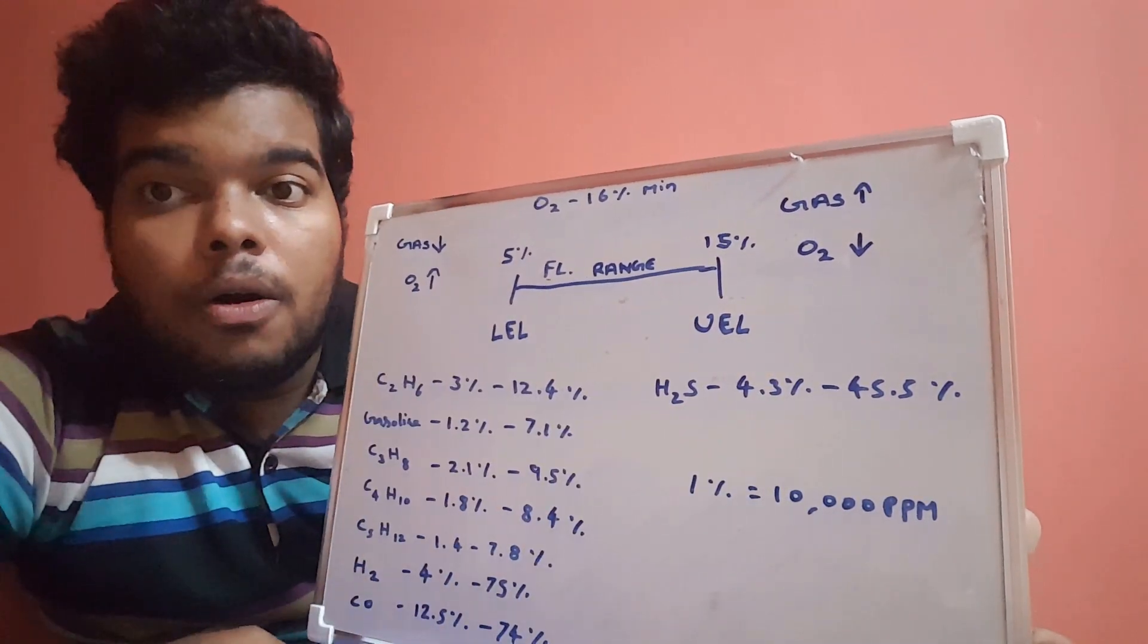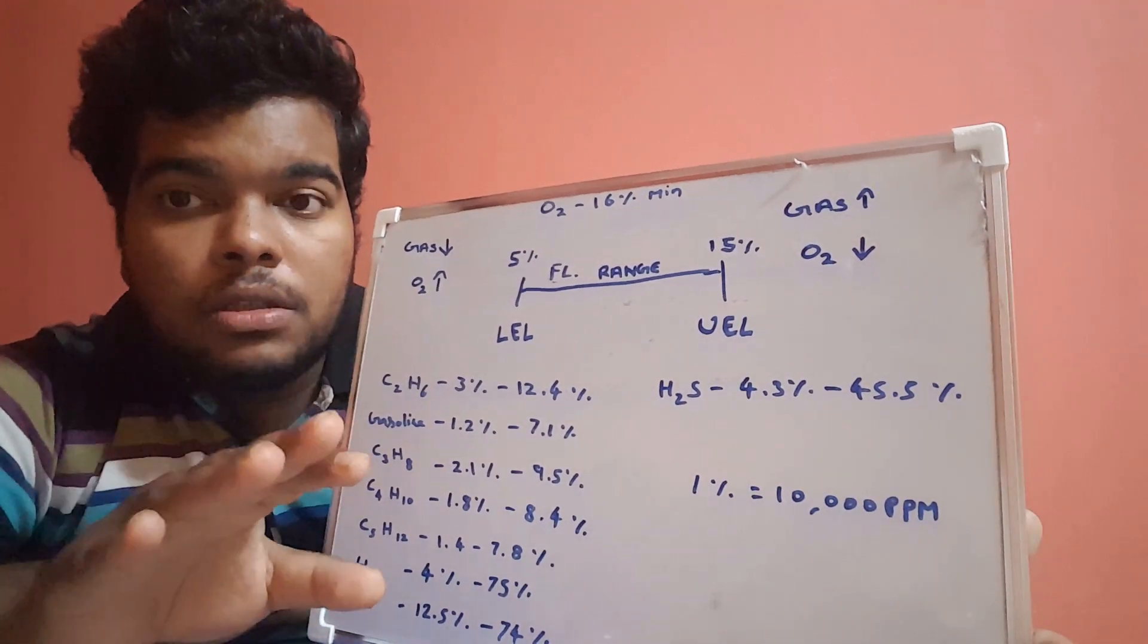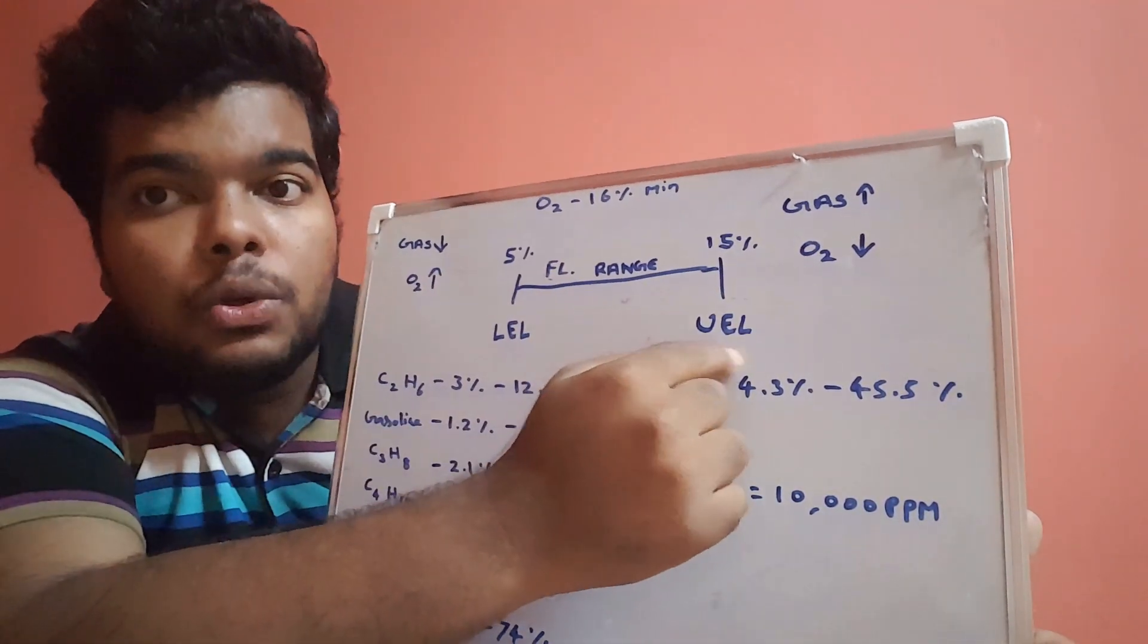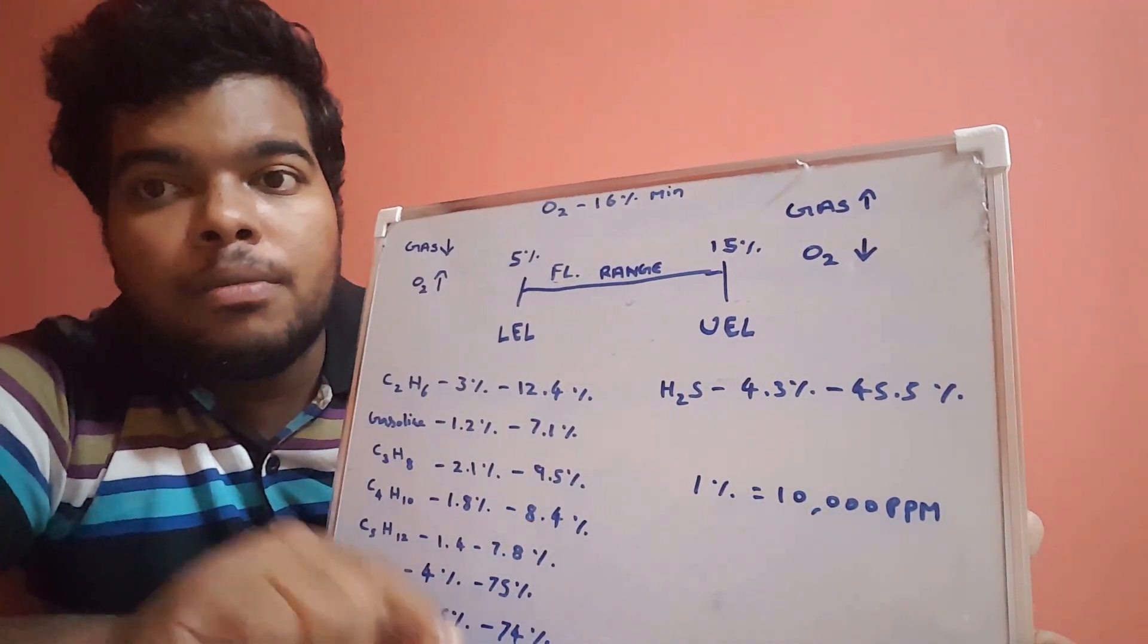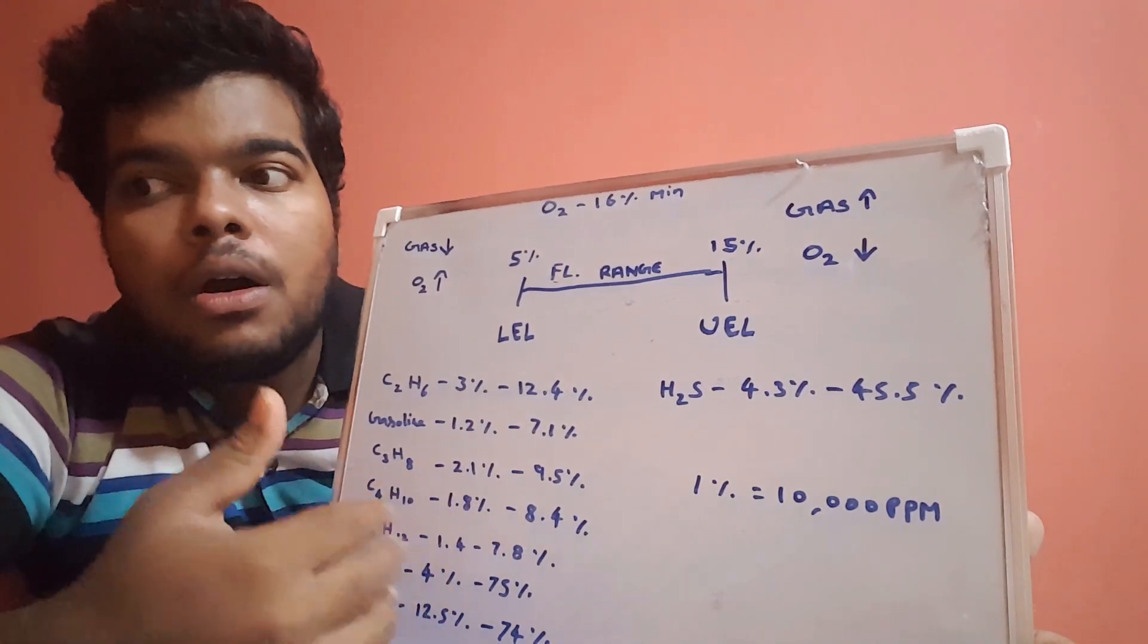The oxygen level will go down, so before turning on this UEL alarm, the oxygen low-level alarm will turn on definitely. Below 19.5 percentage, definitely the oxygen alarm will be on and we won't get this UEL value at that time.